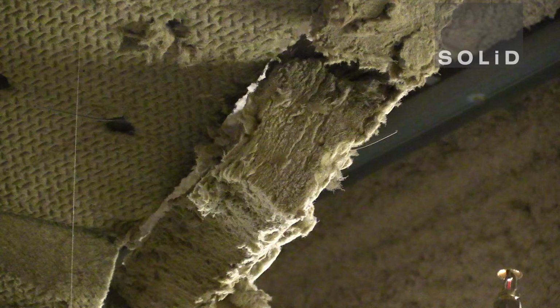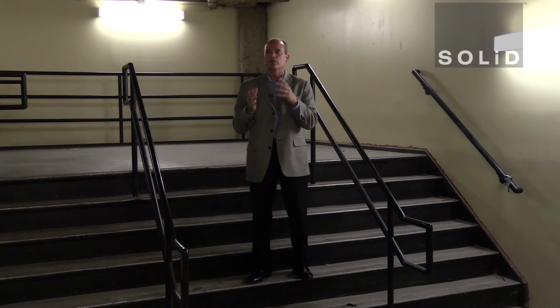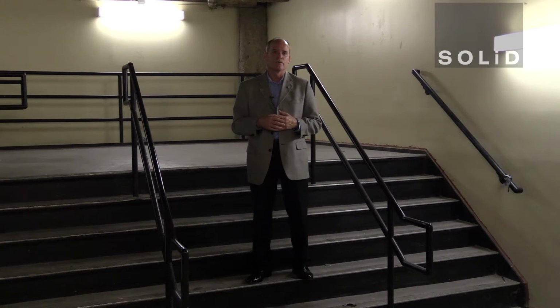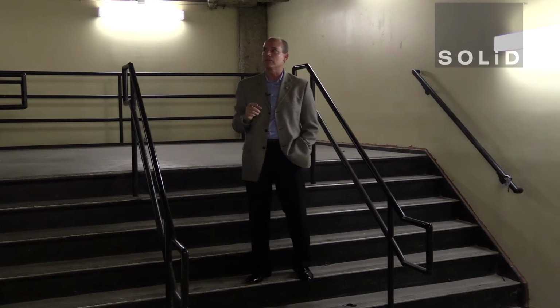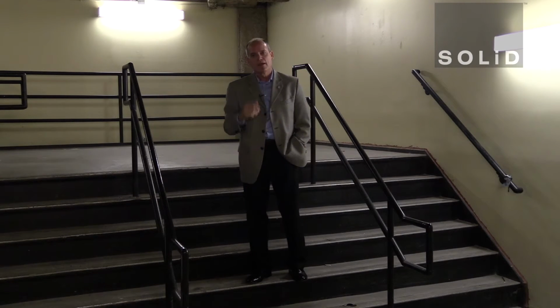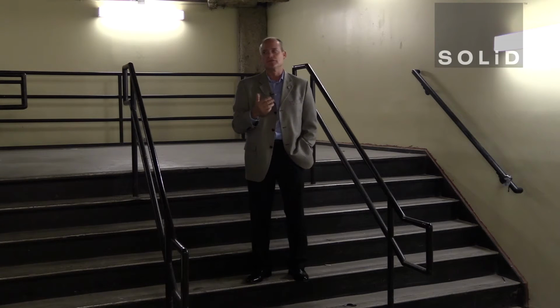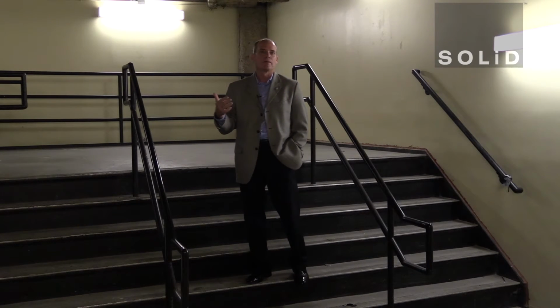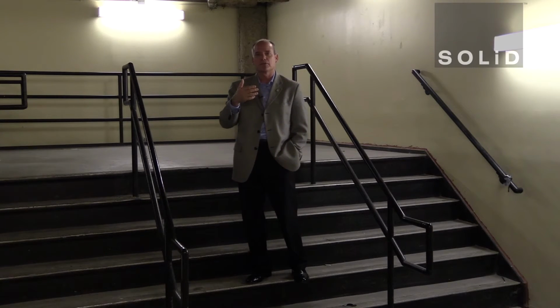But if you look right here, you've got some fireproofing coming off. What happens oftentimes is folks come in to mount equipment, whether it's unistrut or whatever, to hold your DAS equipment, and they'll just scrape some of that off, and that way they can put their C-clamp right on that steel I-beam like these sprinkler clamps are. The problem then is you have to come back and reapply that fireproofing. So it's an addition to your contract that you probably didn't plan on, but the fire official is going to say it has to be redone because it was required to be there to start with.